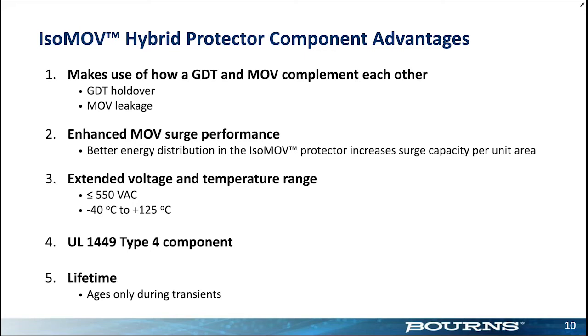Now, number two, not only have we put a GDT inside the MOV, but we've optimized the current density through the MOV. If you look at the forensics of MOVs that fail, and I use the word fail, that's unfair. It's really end of life. These things do have a finite lifetime. GDTs and MOVs both have finite lifetimes. But when you look at how they enter this end of life, you'll see there's pinholes at that metallization contact. What's going on there is that there's current crowding. These materials are not perfect.